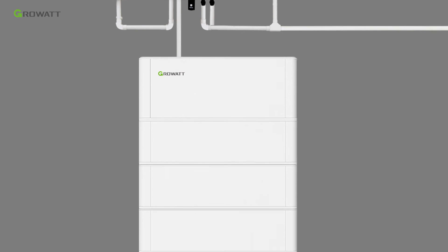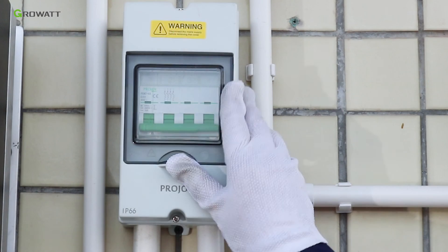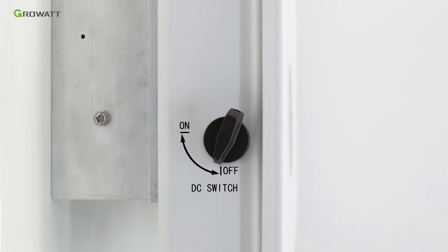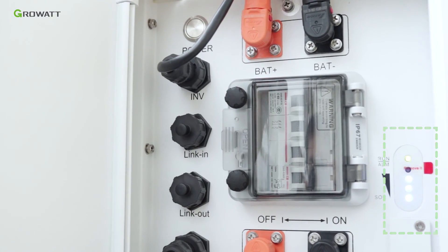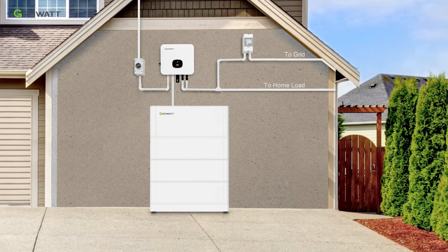As demonstrated, you can see the whole ESS system. Now we start to power the whole system. First, turn on the breaker between the grid and inverter. Second, turn on the PV breaker and PV switch of the inverter. Finally, turn on the breaker of the power module and power on the battery system. The status indicator will flicker for a short time and then remain always on. The MODXH series battery-ready energy storage system includes the MOD10KTL3XH, ARK-XH battery system, smart meter, and AC breaker between the inverter and the grid.